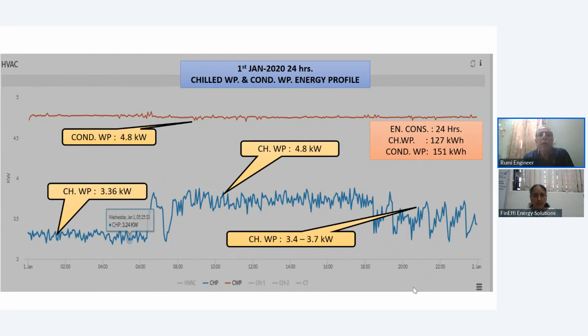The condenser water pump consumption went up to 14 and 13 because 2 or 3 pumps were started when not required. The VFD was bypassed, and it must have happened at night. If you check the time, it's 4 o'clock, third shift.